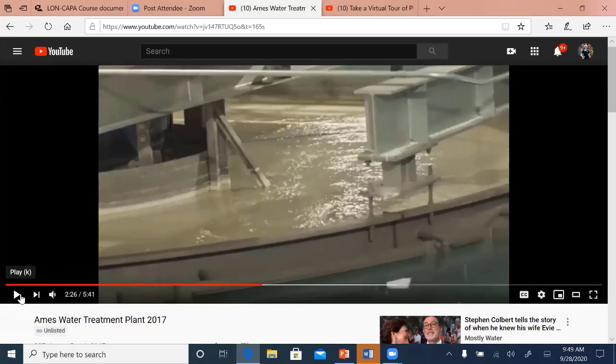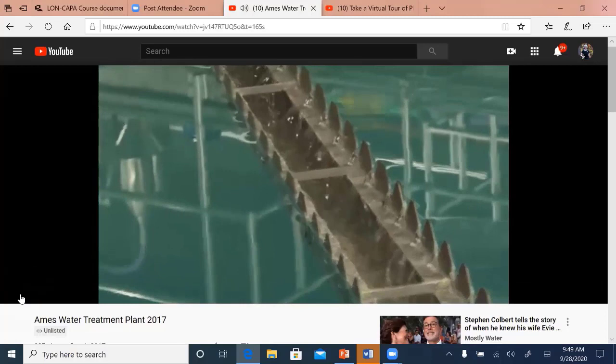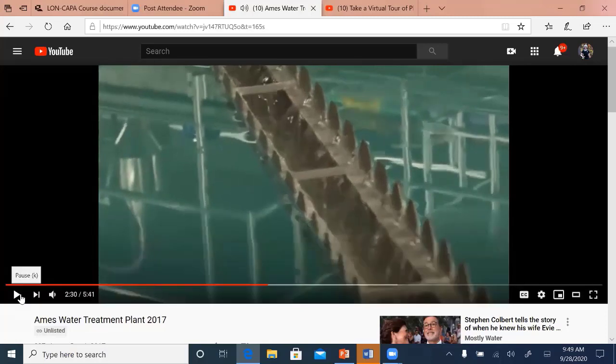So you can see the mixing occurring in the middle. You don't see the flocculation because it's in that inverted cone under the sedimentation basin. As part of the solids contact process, carbonation. This is a weir. So you can see, I drew the arrows, that the water flows up through the sedimentation basin, through that sludge blanket, and then out over a weir into a channel, and then it would move into a larger channel onto the next unit.